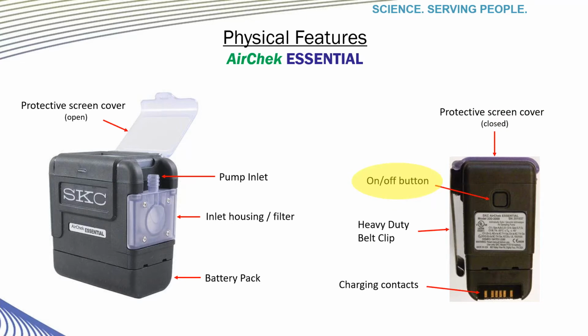The on-off button serves a couple of purposes, as you will see later in the operation training. When the pump is off, it turns on the pump and the display. If the pump is not in the run mode, the button will also turn the pump back off. However, if the pump is in the run mode, pressing the on-off button will lock the display for a second level of security against tampering. This is another great improvement on this family of pumps.